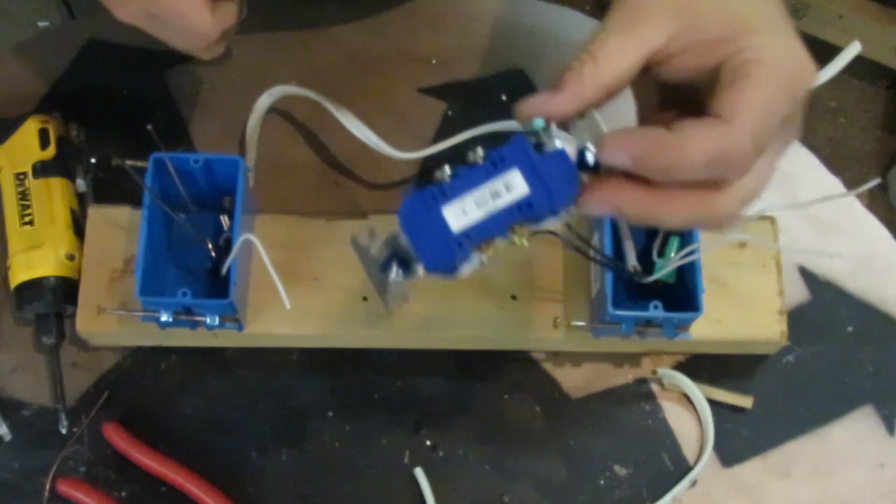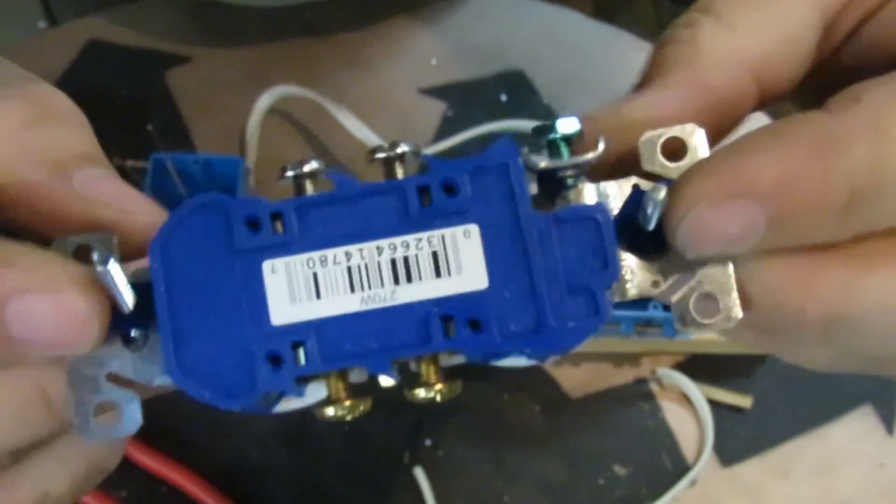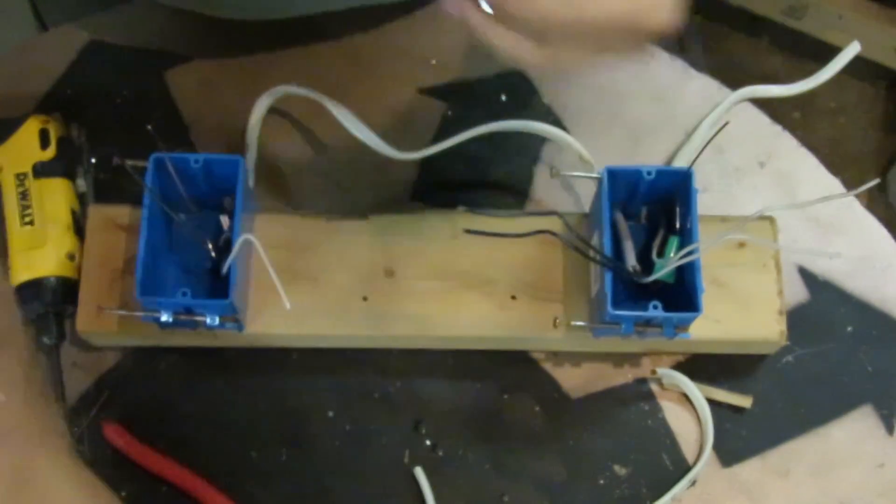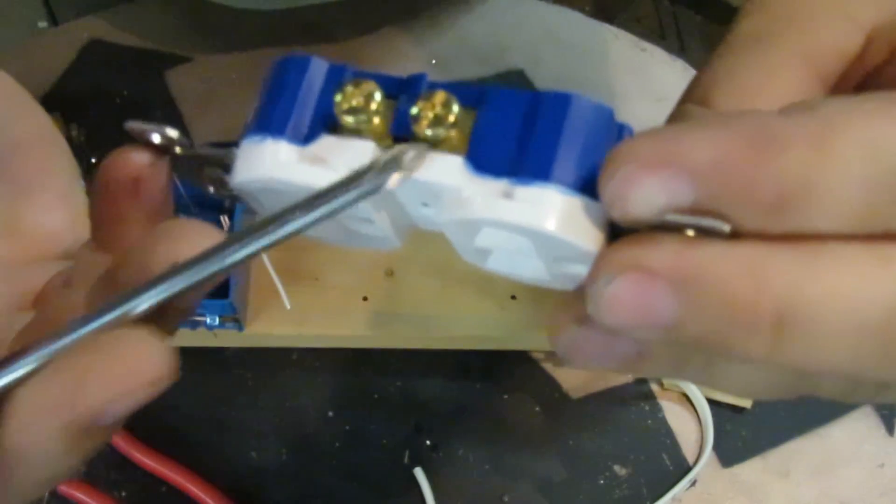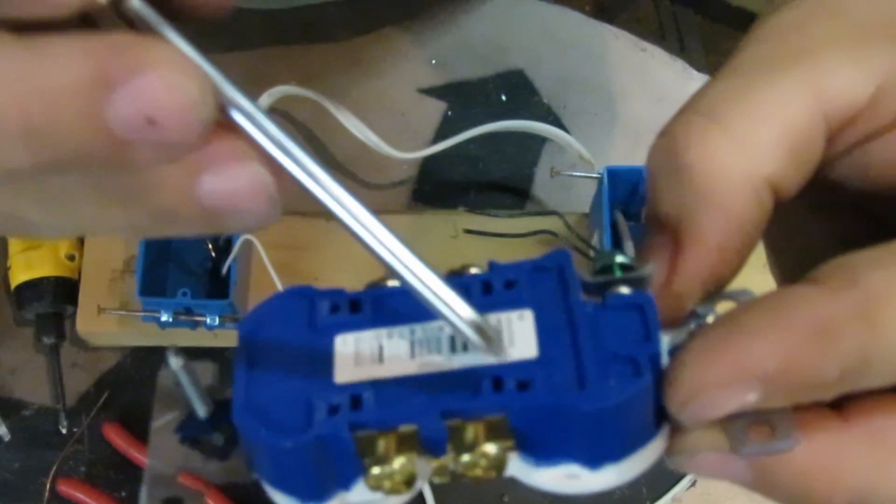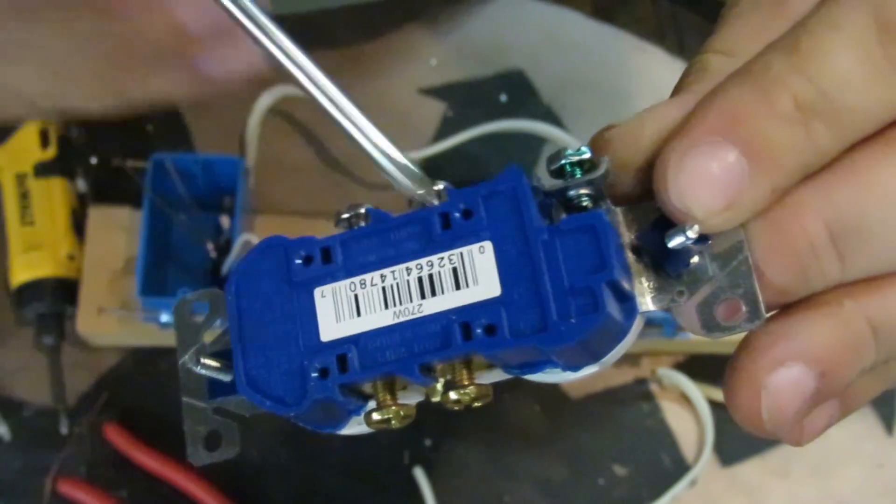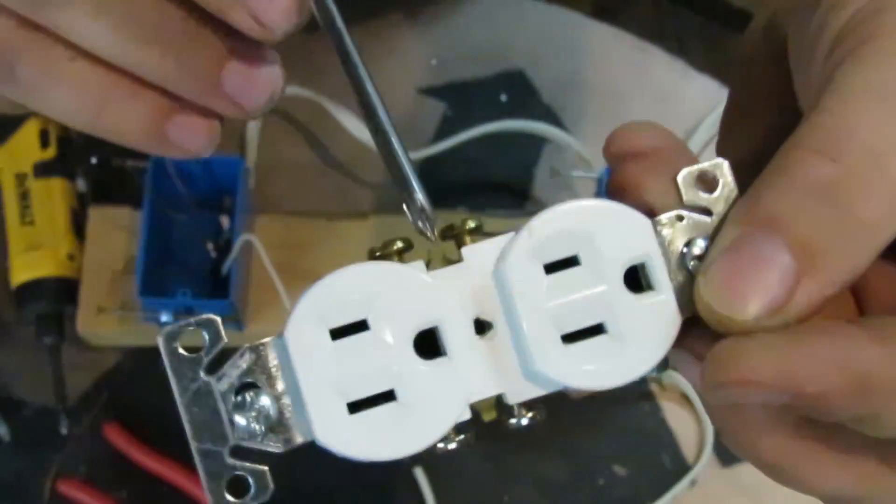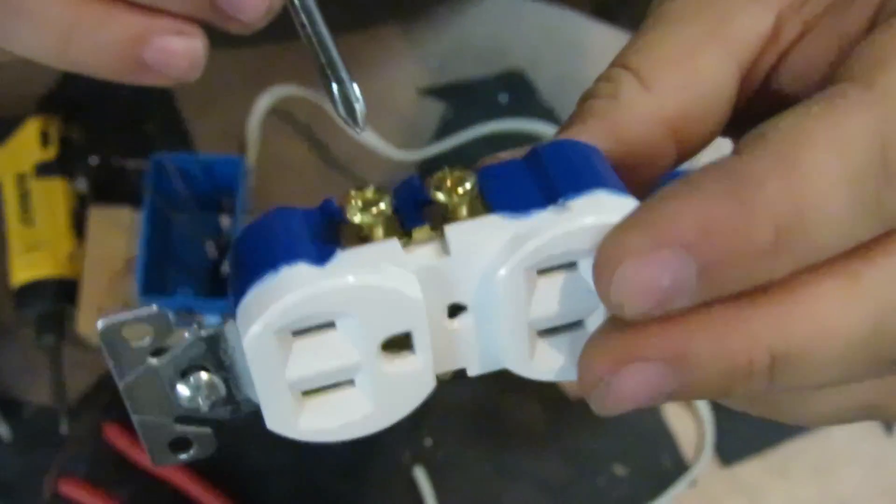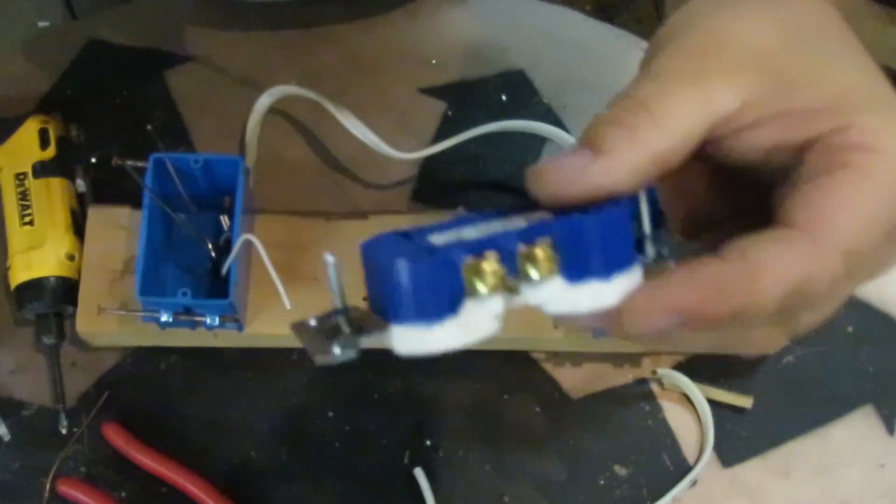Well, your typical receptacle is going to look like this. As you see, there's one side that has two brass screws and two holes in the back, and two silver screws and two holes in the back that correspond. And there's also these little breakouts that you can break out and you would separate the top screw and the top hole from the bottom screw and the bottom hole.